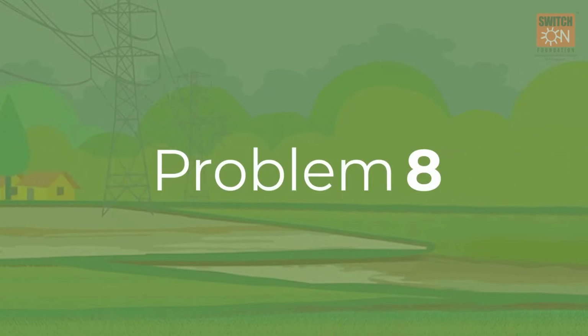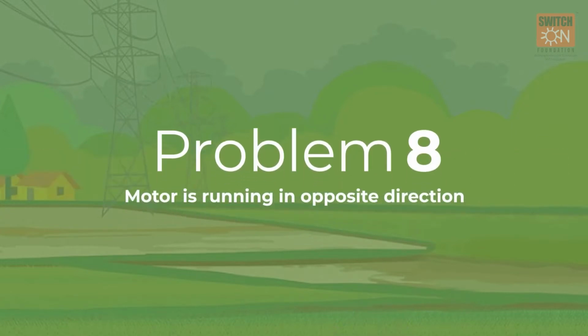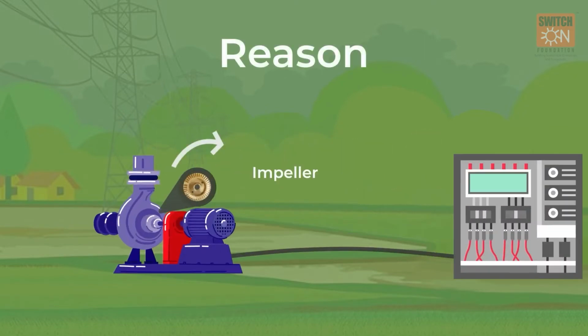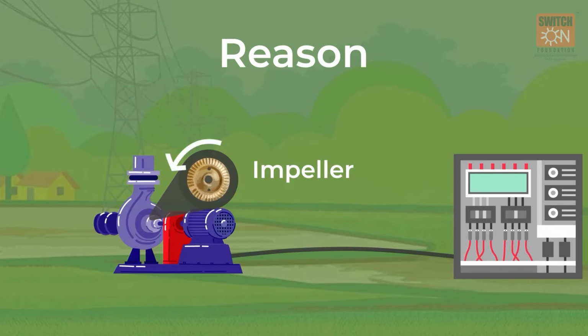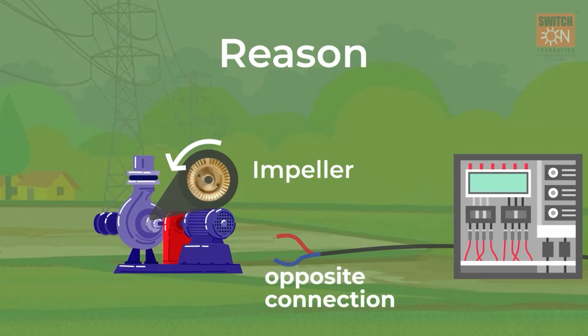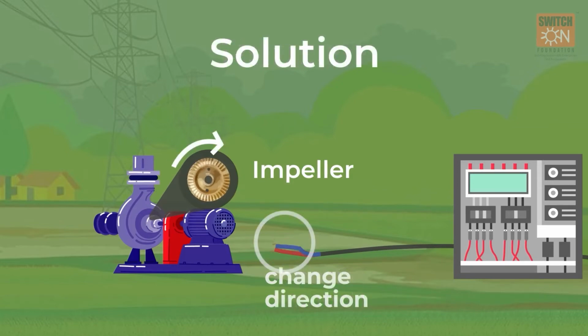Problem 8. Motor is running in opposite direction. Reason: water pumps are designed to operate with the impeller going in one direction. If it is going in the opposite direction, then there is an opposite connection between the controller and the pump. Solution: the direction of connection needs to be changed.